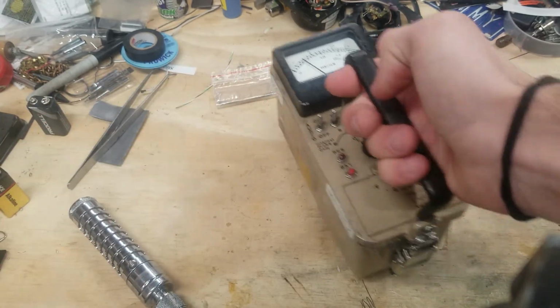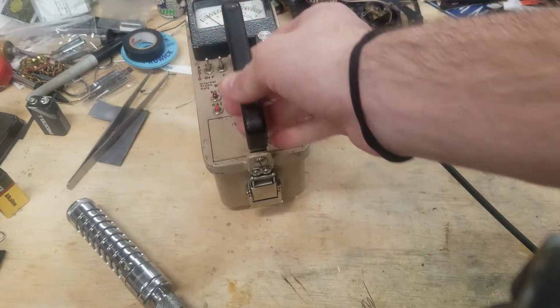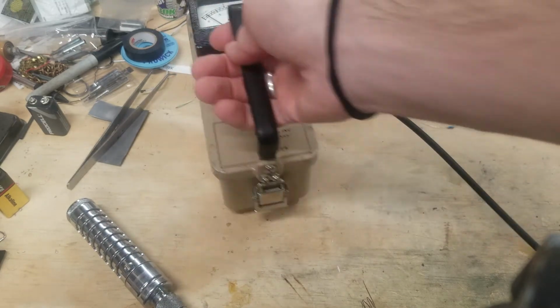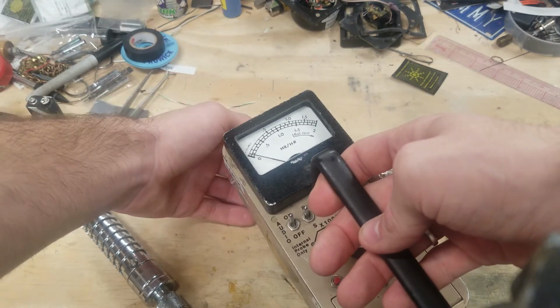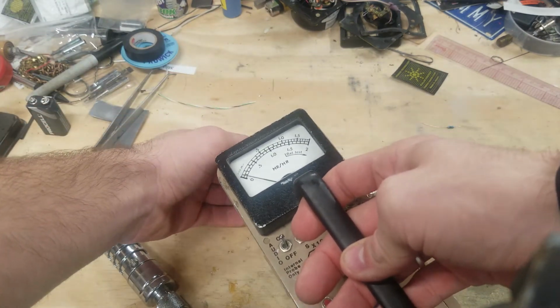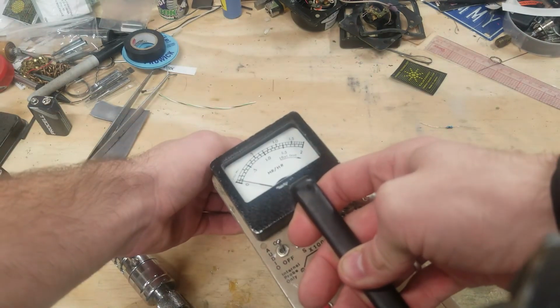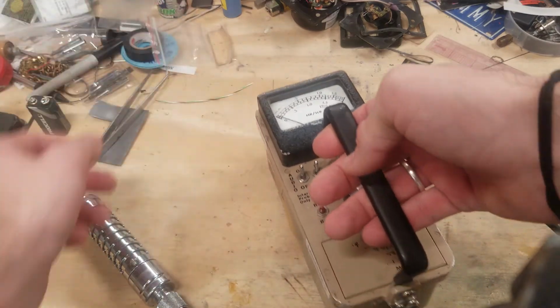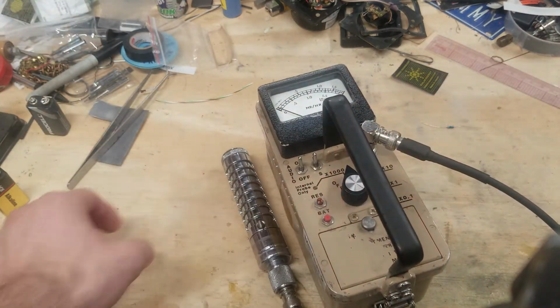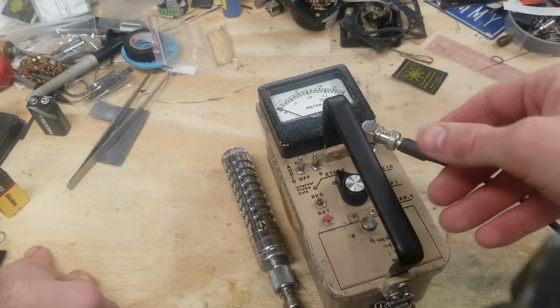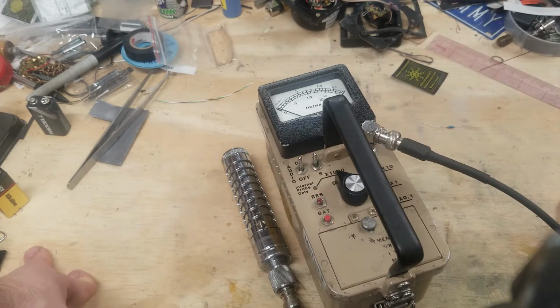But because of the high range, we have the benefit of being able to test on a higher setting. In this case, it's still not enough to move the needle. It's a very hot source, but 1.5 R is a very high setting.